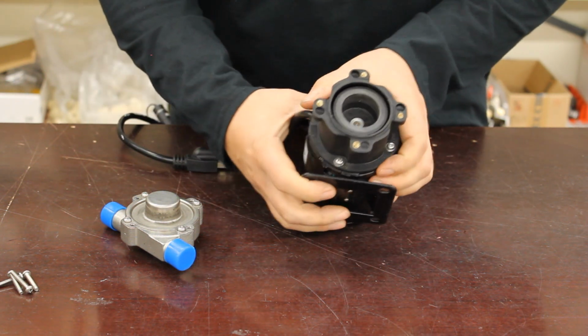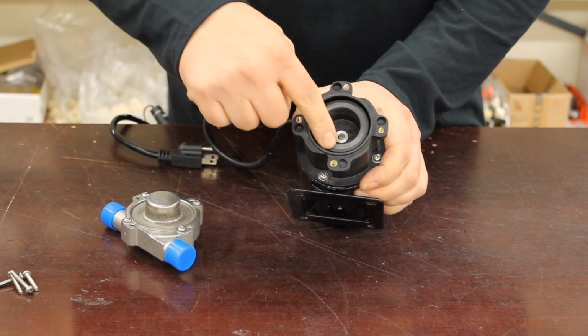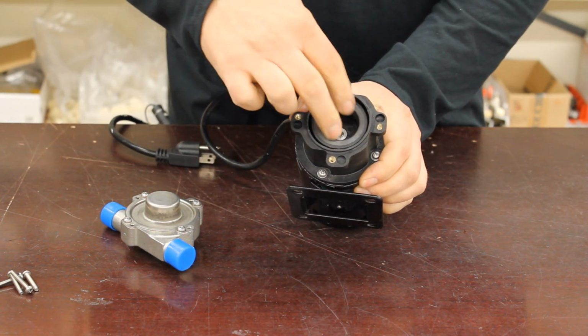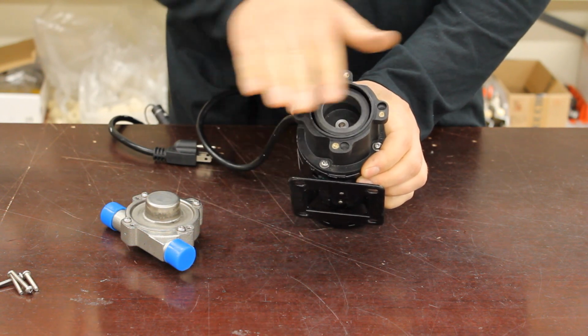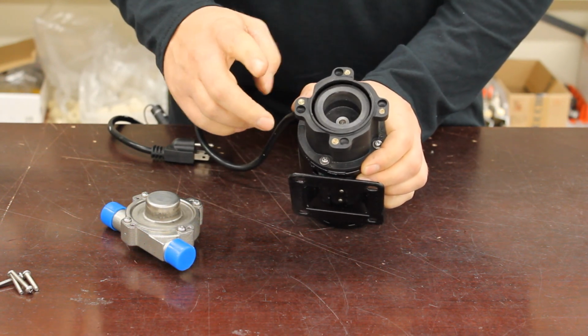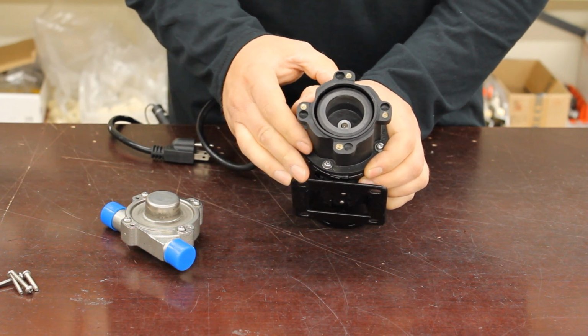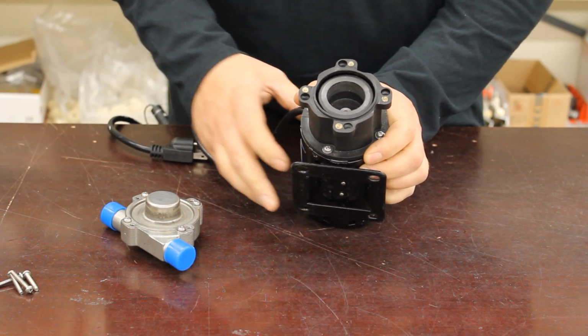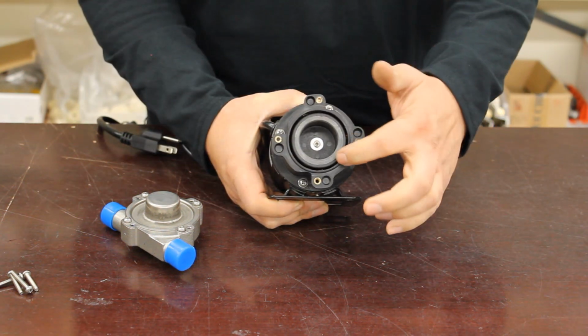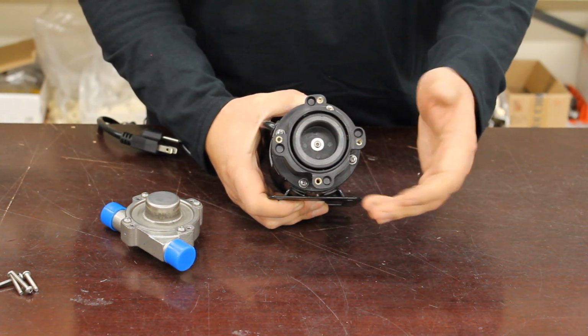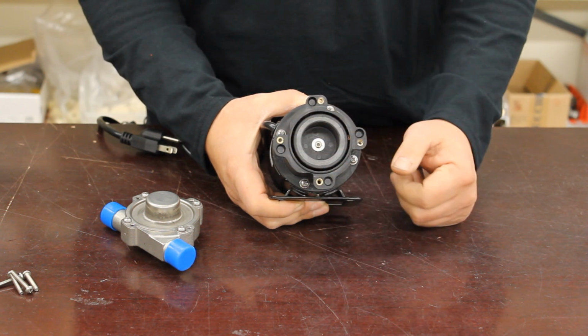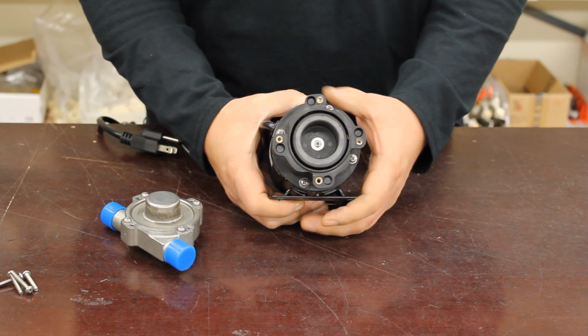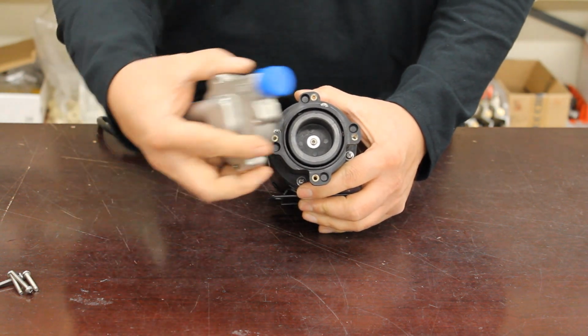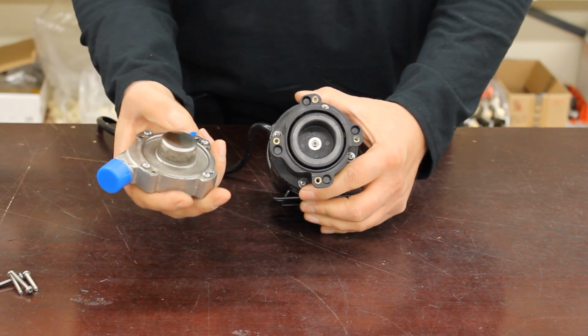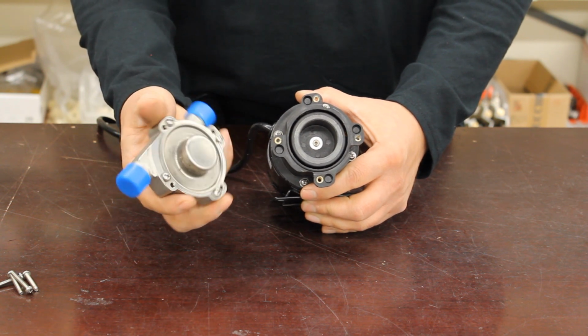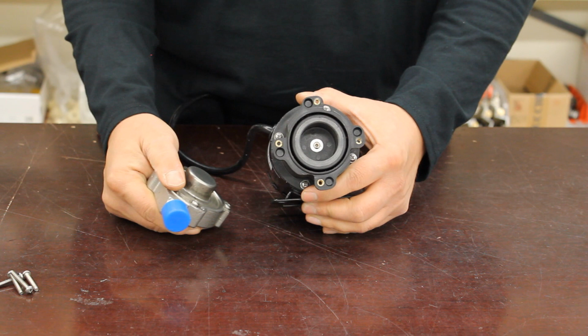Now, one thing I want to bring to your attention is that the cup magnet is attached to the motor shaft, so that really can't move left or right or up or down. But the mounting ring or head mounting bracket does have a little bit of movement capability. Now, I'm not sure if you can see it, but the cup magnet here is not concentrically centered in the opening of the mounting bracket. And what that means is that when the head is attached to the mounting bracket, this impeller protrusion here is not going to be perfectly centered within the cup magnet.